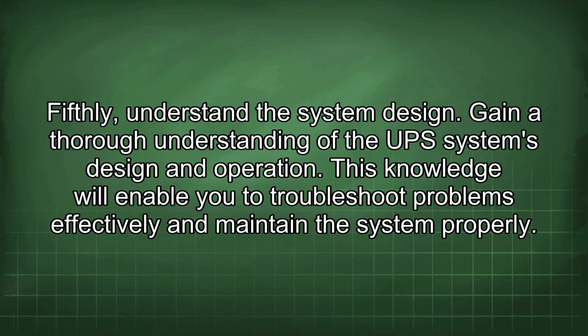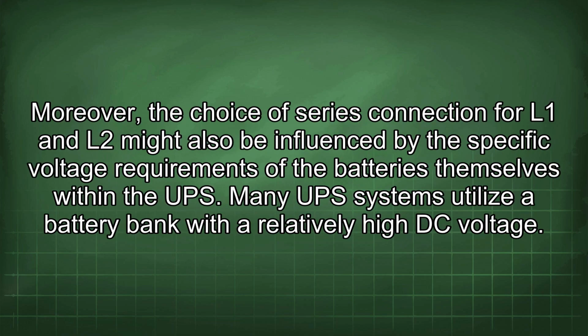Fifthly, understand the system design. Gain a thorough understanding of the UPS system's design and operation. This knowledge will enable you to troubleshoot problems effectively and maintain the system properly. Moreover, the choice of series connection for L1 and L2 might also be influenced by the specific voltage requirements of the batteries themselves within the UPS.